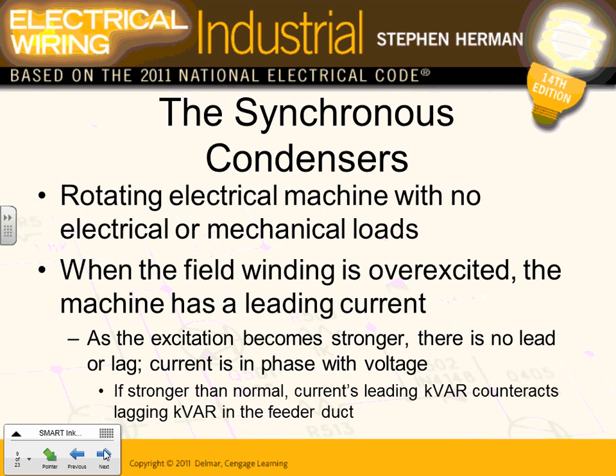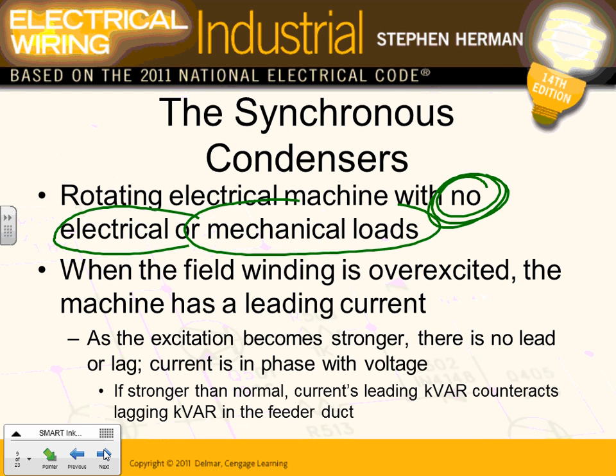So correcting power factor happens in two ways, Adam. One is a capacitor, and the other one is what? The so-called condenser. These are rotating machines with typically no load, no mechanical or electrical load on them. The rotor is spinning there inside your building, and they overexcite these synchronous machines and they start generating VARs for you. So that's the concept. Overexcited, putting more DC into the rotor, it starts creating a leading current or a leading VAR, and that leading VAR counters the lagging VAR that's coming from the other motors.